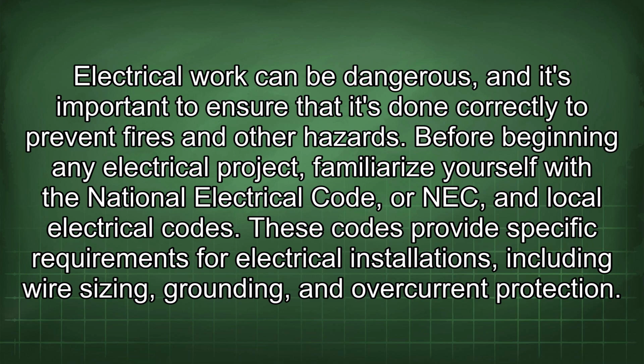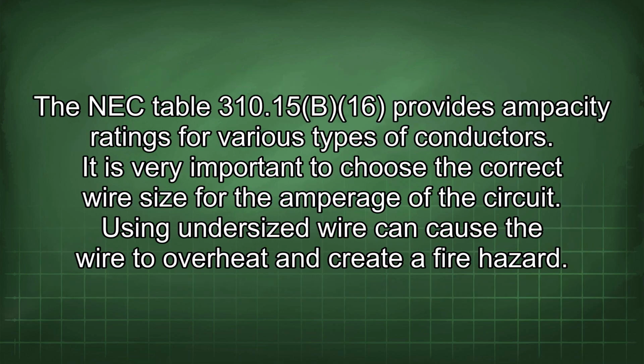Before beginning any electrical project, familiarize yourself with the National Electrical Code, or NEC, and local electrical codes. These codes provide specific requirements for electrical installations, including wire sizing, grounding, and overcurrent protection. NEC Table 310.15(B)(16) provides ampacity ratings for various types of conductors. It is very important to choose the correct wire size for the amperage of the circuit.